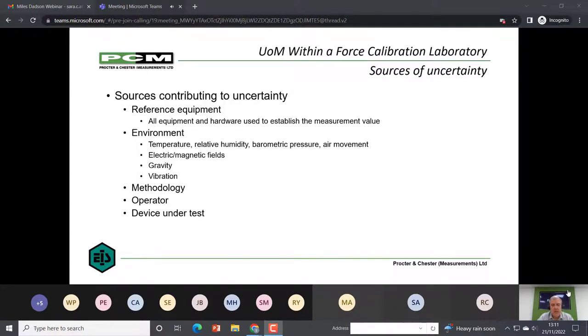Then there's the operator. Is the operator showing any bias, both conscious or unconscious? And is that operator allowed some level of scope in the calibration procedure? I.e., is the calibration procedure prescriptive, or does it leave a little bit to the user's inference? And then you've got the device under test as well, what foibles, what mechanical interfaces are associated with the device that's being tested. And at the end of the day, when you've had a calibration conducted, all you can really say is, on that day, under those conditions, by that methodology, the results were. It's a bit like an MOT for a car. The moment you drive the car off a forecourt from an MOT, the MOT is somewhat moot.